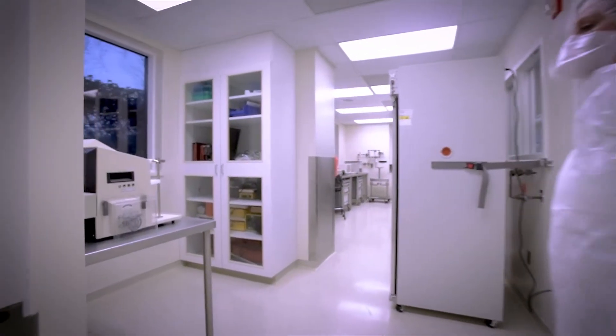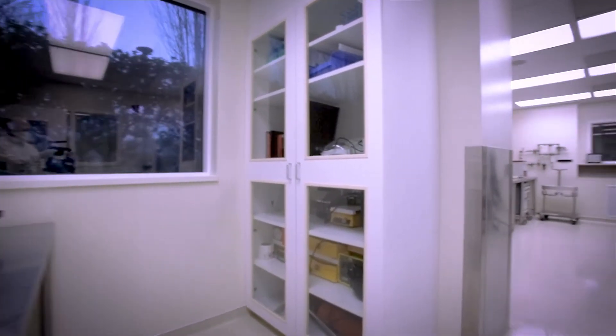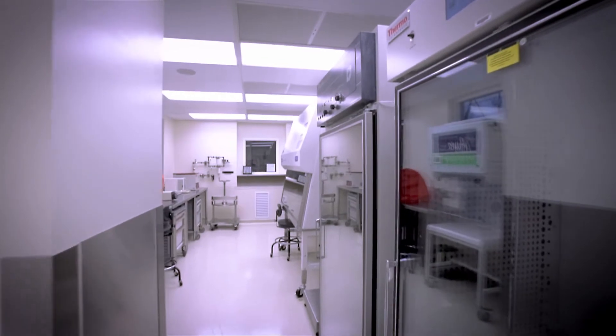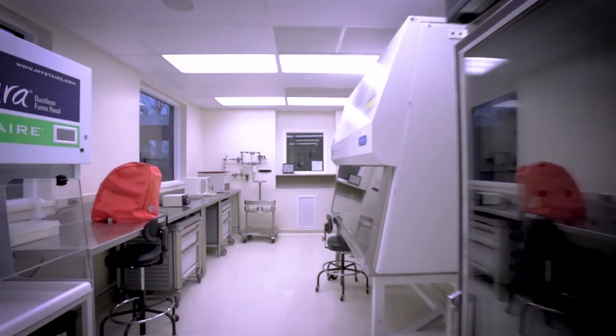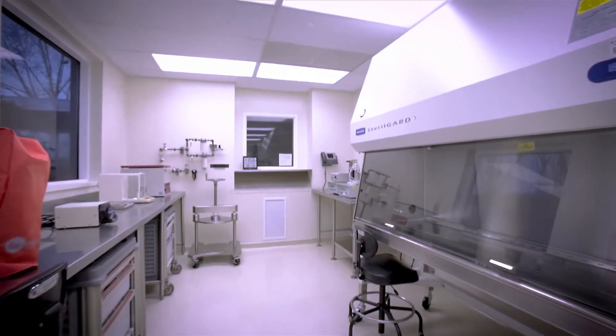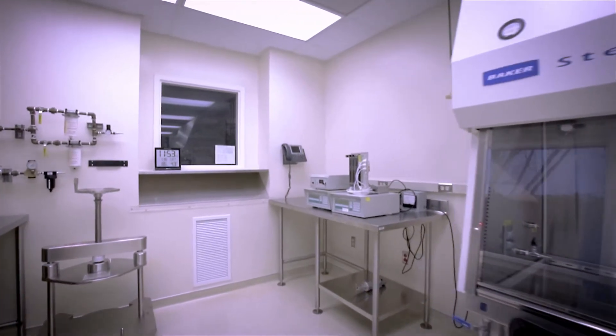The first suite on the right is the production suite in room CD163. This suite is class 100,000 using single-pass HEPA filtered air. The suite contains two CO2 incubators, a six-foot biosafety cabinet, and a fume hood. USP-grade gases are supplied by an outside vendor to support clinical bioreactor production. Upstream processing as well as lentiviral vectors are produced in this suite. Equipment can be moved in and out depending on the process.